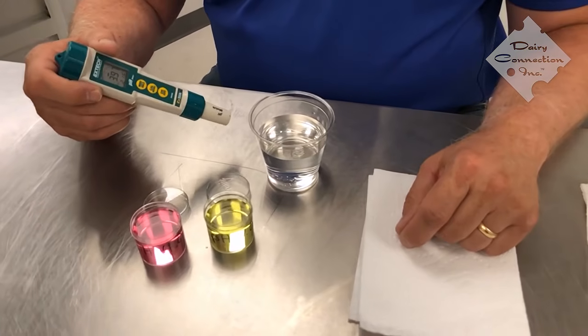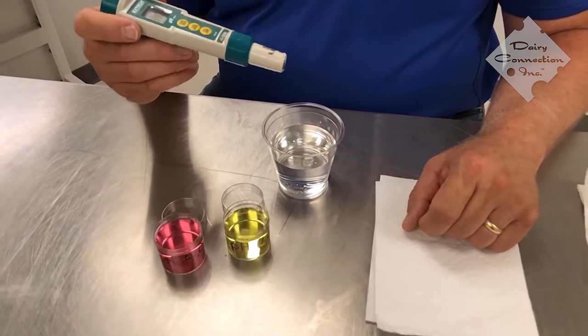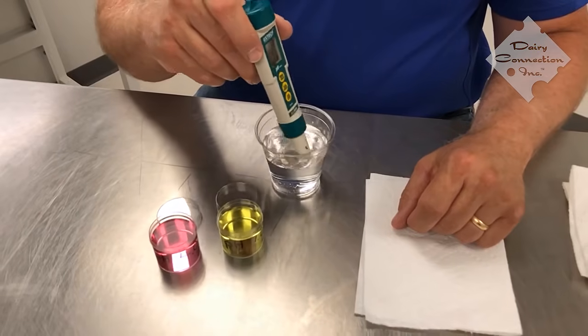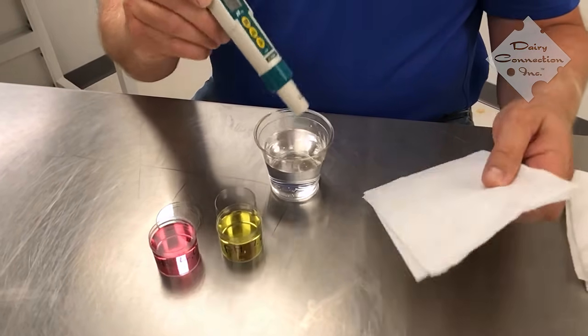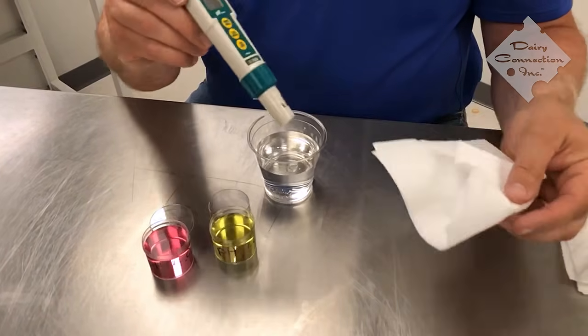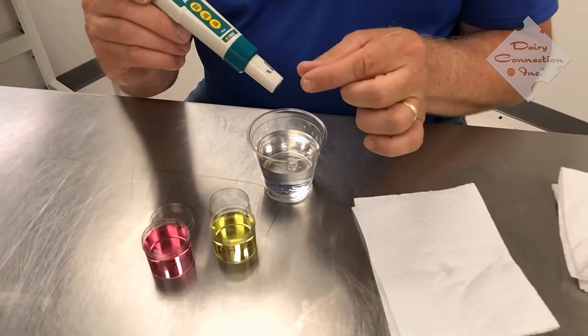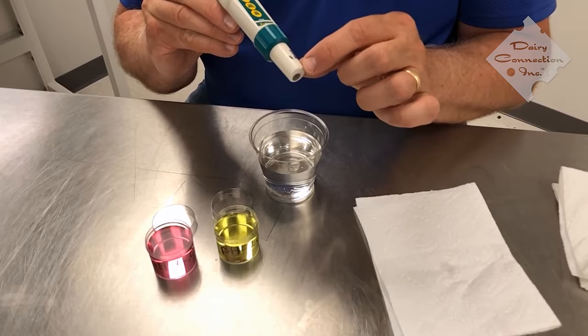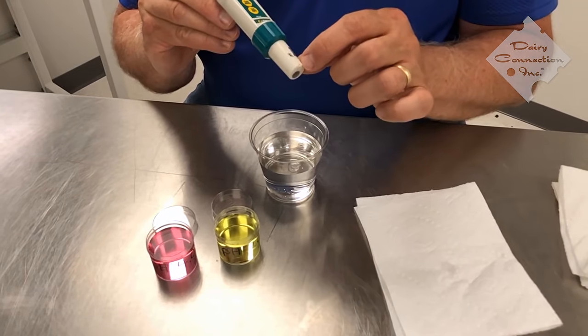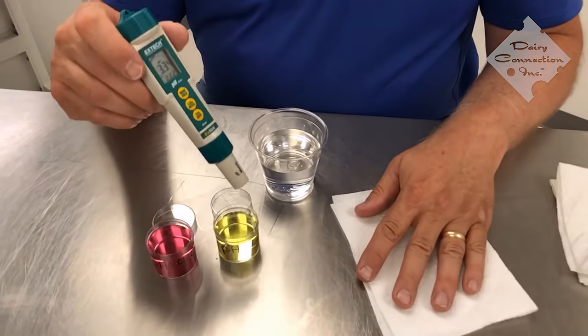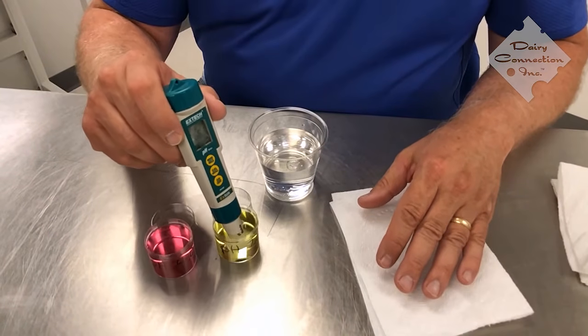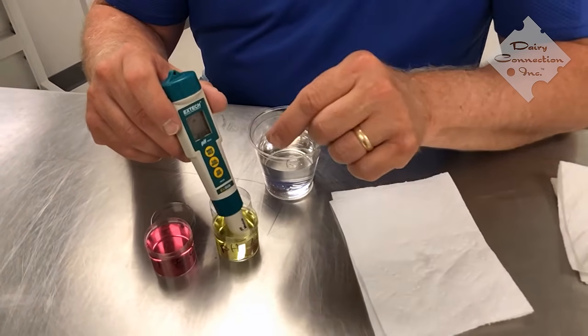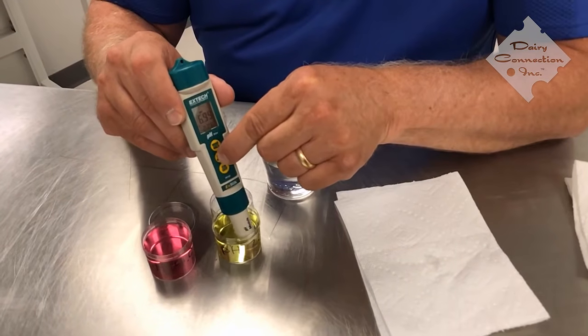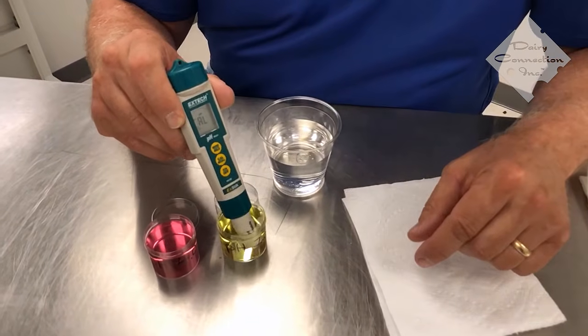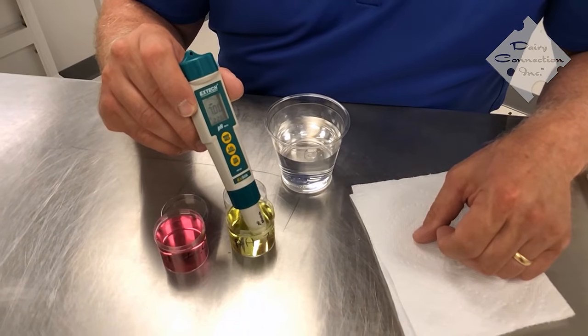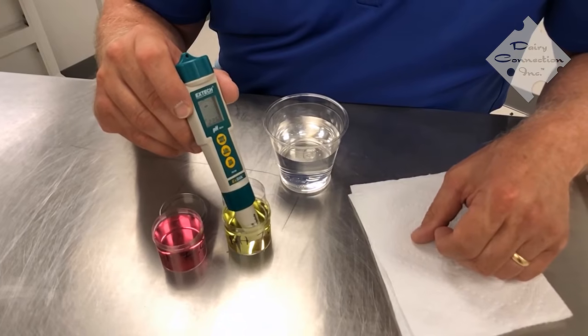So the first step in calibrating your pH electrode is to make sure the electrode is clean. And I rinse that off in distilled water, and I blot it dry. I always recommend distilled water because tap water can leave a calcium deposit on the end of the pH electrode where the sensing takes place, and that can block that measurement. To calibrate, we want to go with the first neutral pH, which is a 7. And on this electrode, there is a middle button called Calibrate, C-A-L. You stick it in the 7, and you can see that it is going through its process. And when it reaches an endpoint, it will say End.